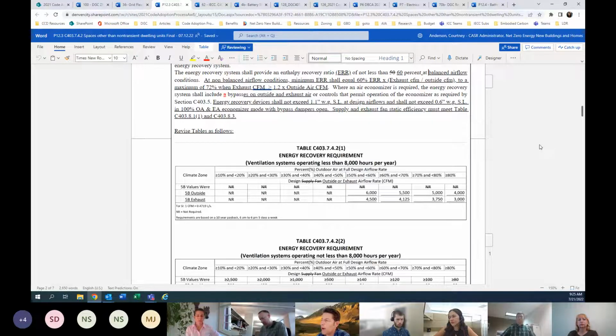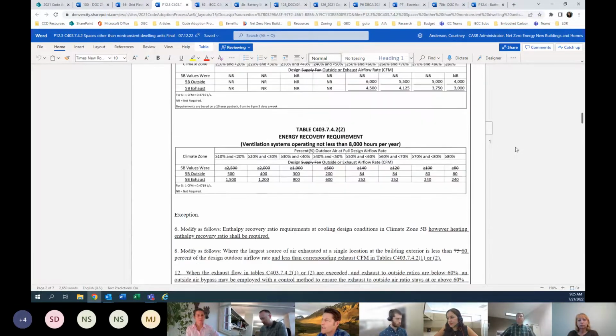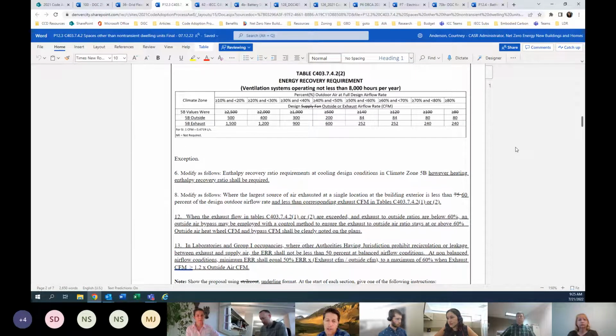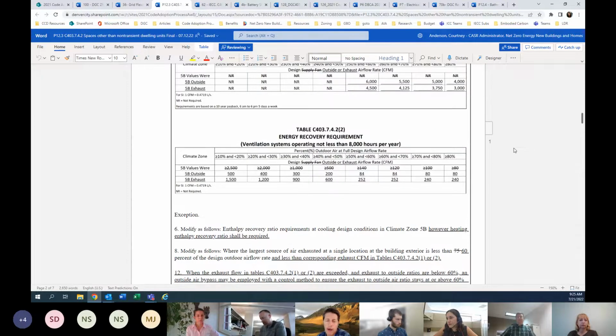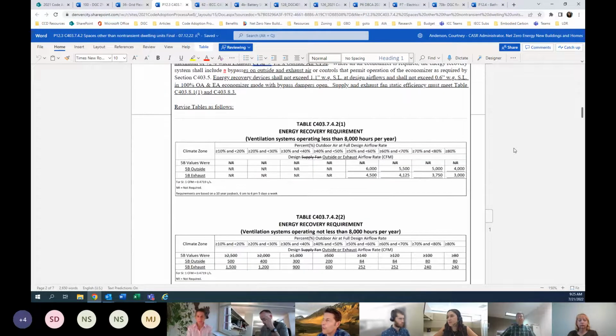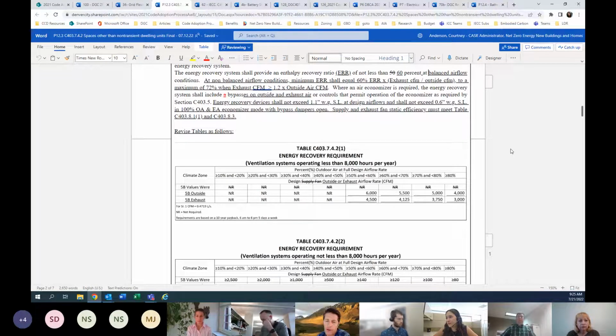And then lastly, currently there's an exception in the code for supply fan efficiency. If you scroll back up, sorry, just a little bit. I'm talking about the very last point. And so the supply and exhaust fan static efficiency, just clarifying that it has to meet the table, because there is an exception for packaged equipment where they can just use the brake horsepower per CFM, which at low statics allows you to have, we calculated 35% efficient fans, which really is, that then you can end up with a product that has a parasitic load. So there's a lot there.